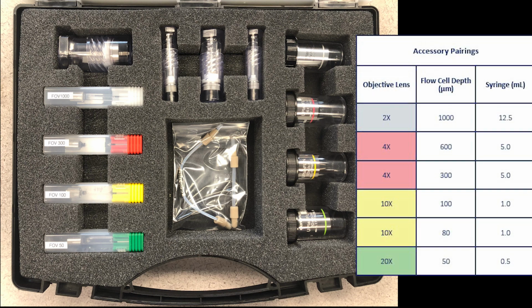In your hardware and accessories case, you will find your magnifying objective lenses, microfluidic tubings, FOV flow cells, and pump syringes. Your FlowCam is calibrated at each magnification with defined accessory pairings. You can find this chart in the FlowCam 8000 series configuration guide, a technical note in your desktop resource folder. In this demonstration, we will be using the 10x magnification lens with the FOV100 flow cell and the 1 mL syringe.